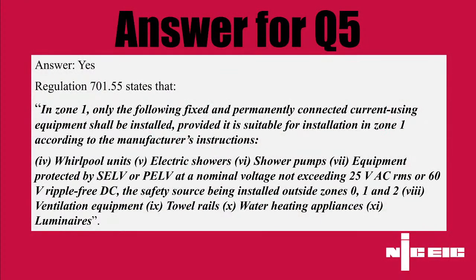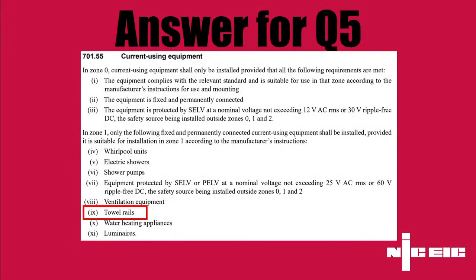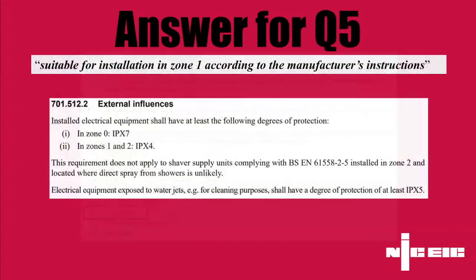Yes, but you want to start referring to regulation 701.55. And again, this can come back to our trusted manufacturer's instructions. In zone 1, that regulation gives you a list of items of equipment that can be installed in zone 1, according to the manufacturer's instructions, and I think item 9 is for towel rails. And then if you look a bit further down, it does say the degree of protection installed in zones 1 and 2, for example, is IPX4.